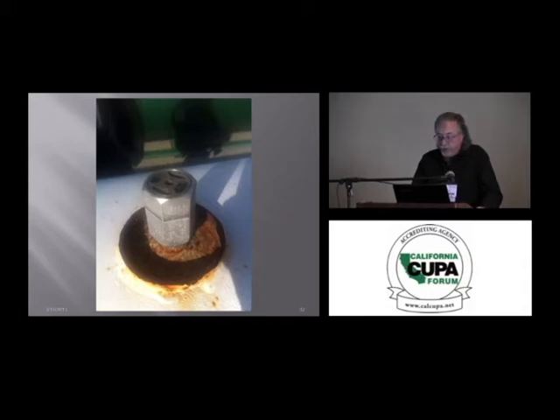They replaced it. But I also identified a pressure switch that had a brass fitting in it when I was there. I gave them till the weekend to replace it. They didn't replace it. Guess which fitting let loose and gassed out the neighboring company about 6 months later. That was the fitting that we found.